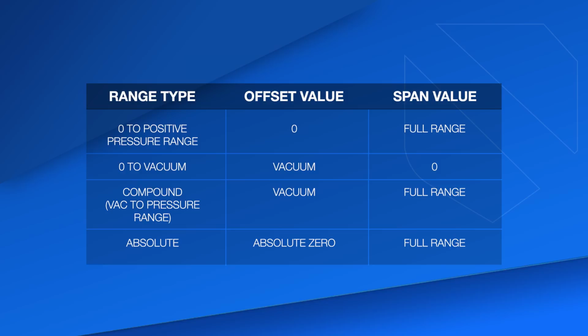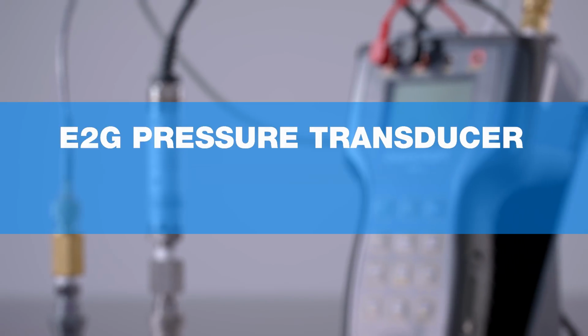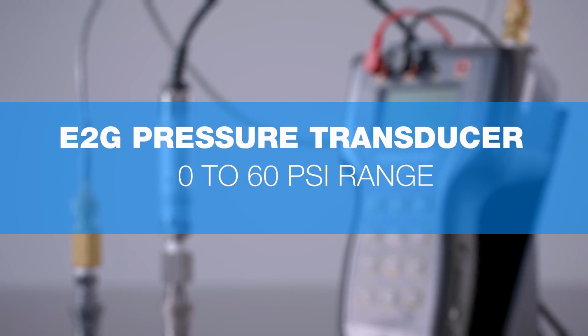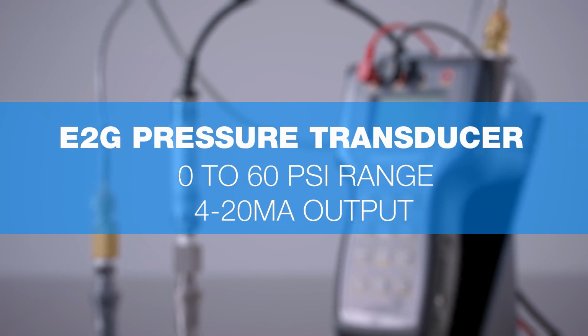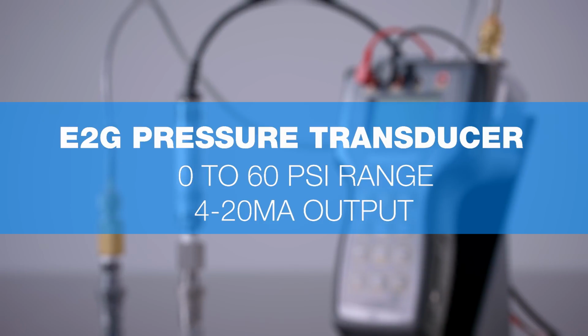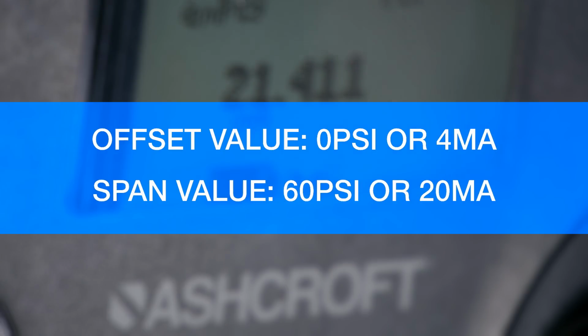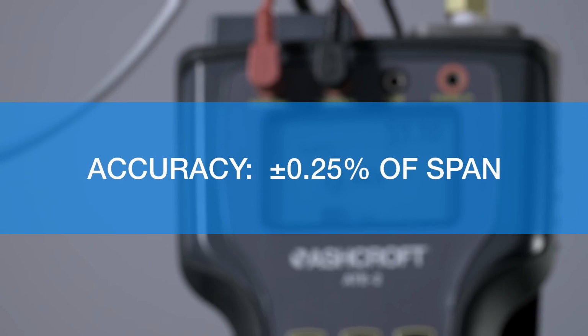The procedure is simple. The first step is to determine the offset and span values for the transducer you're going to calibrate. We're going to calibrate to a 0 to 60 psi range with a 4 to 20 milliamps output. Our offset value is 0 psi or 4 milliamps, and our span value is 60 psi or 20 milliamps. The accuracy for our E2 is plus or minus 0.25% of span or plus or minus 0.040 milliamps.